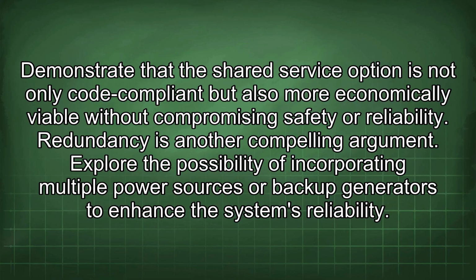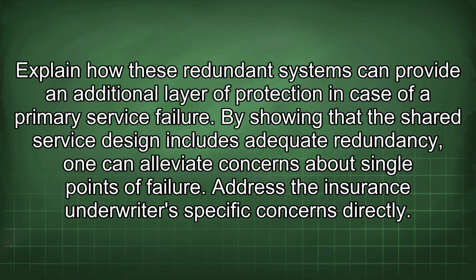Redundancy is another compelling argument. Explore the possibility of incorporating multiple power sources or backup generators to enhance the system's reliability. Explain how these redundant systems can provide an additional layer of protection in case of a primary service failure. By showing that the shared service design includes adequate redundancy, one can alleviate concerns about single points of failure.